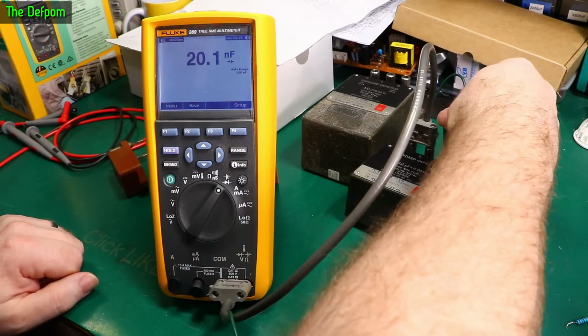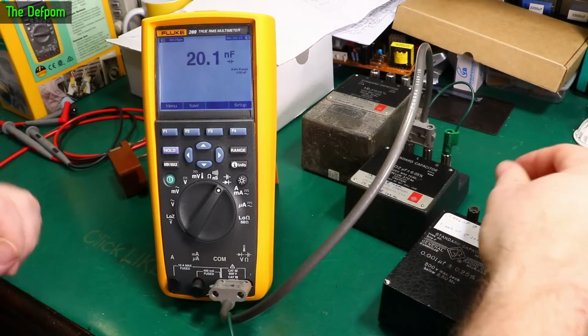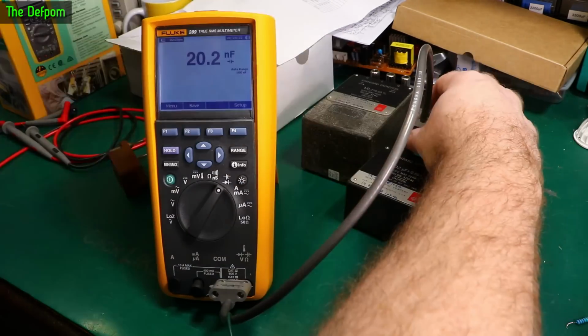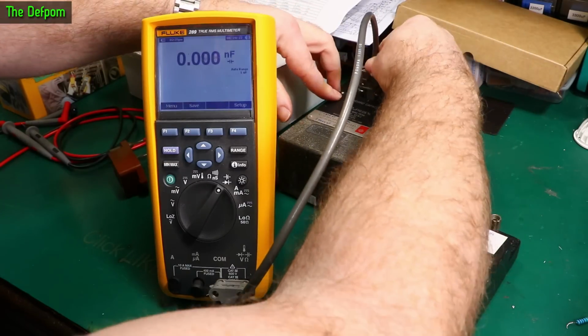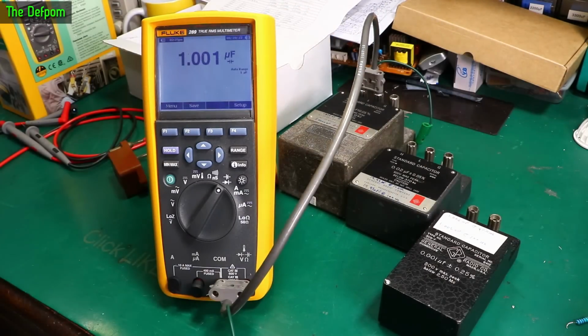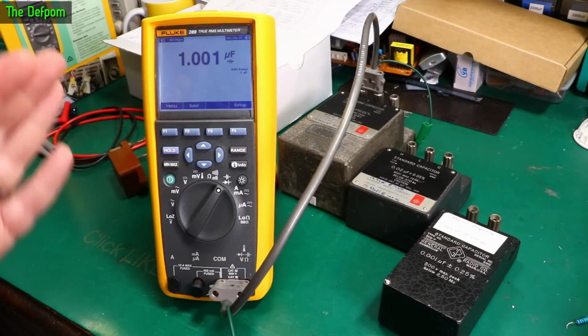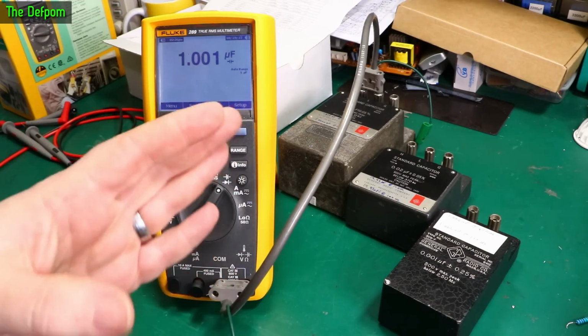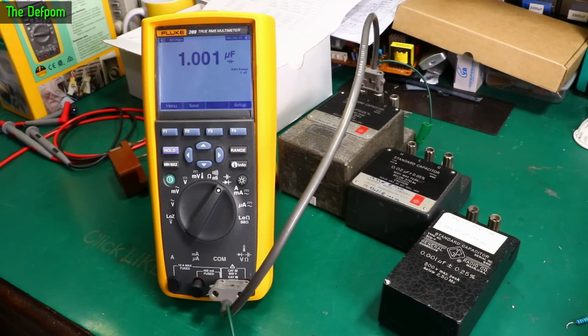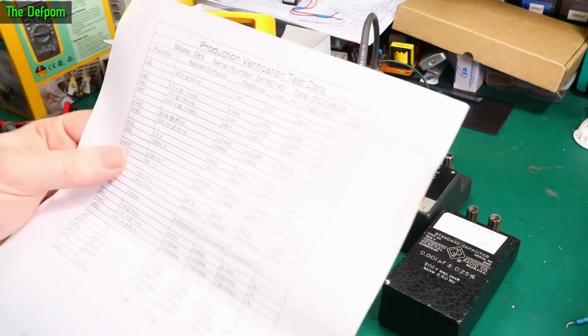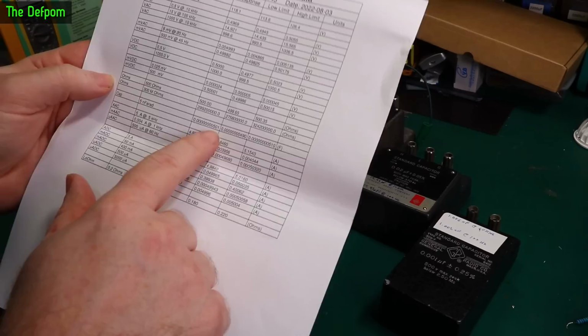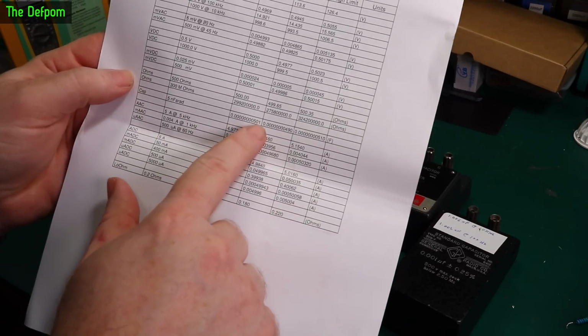Let's just stick with the guarding on there, shouldn't matter anyway. Yeah, fine, no difference. And then we've got 1 microfarad over here, and that's looking really close - just one count up. So they look pretty good, apart from the bottom end, like below 5 nanofarad it would seem, which is where their calibration point is. And the actual reference here was reading very slightly high, 501.